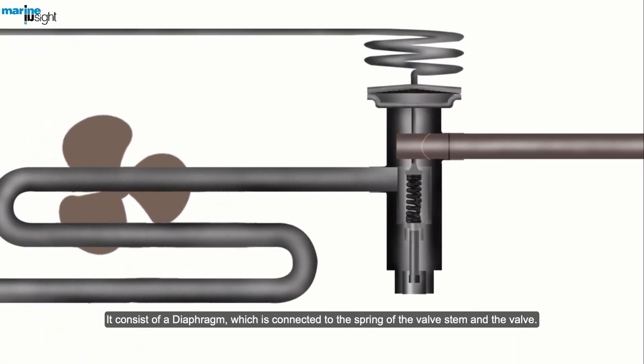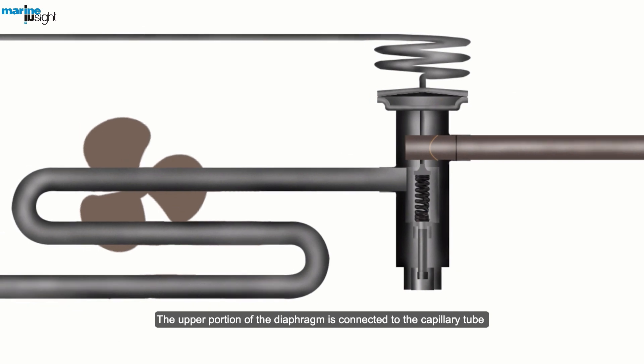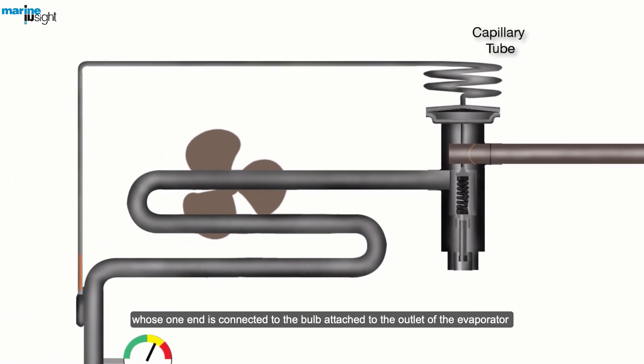It consists of a diaphragm, which is connected to the spring of the valve stem and the valve. The upper portion of the diaphragm is connected to the capillary tube, whose one end is connected to the bulb attached to the outlet of the evaporator containing small amount of liquid in a part of the bulb.